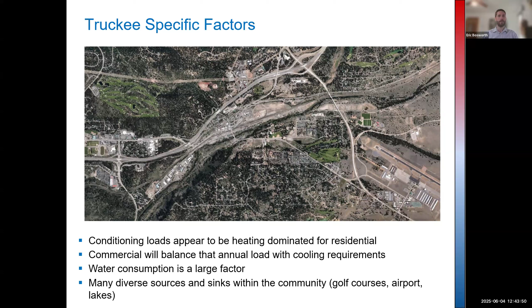You also may have things like breweries, bakeries, other businesses in town that generate a lot of heat that you could potentially capture and reject into the thermal network. The great thing is, rather than getting it from underground, you put it into the pipes, move it up the street, and a residential home may be able to take those BTUs and put them through their heat pump and deploy them back into their building. The efficiency there is extremely high. When systems are running that way and you're exchanging energy, you can see coefficients of performance - a measure of 1 unit of electricity in to 1 unit of heating or cooling energy out - as high as 7, 8, 9 in some cases, simply by pumping water up the street and exchanging heat between customers. It makes for some very efficient and very interesting systems.